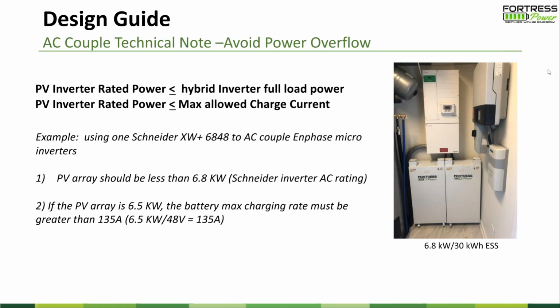And then the PV array - we want to see that it's smaller than the battery bank size. The reason I say this is a lot of PV inverters actually allow you to hook up a little more than what they're rated. If they say it only takes 5K, you can put 6K, because they consider shading, bad weather, productivity, and so on. So that's usually what you want to look at, but we want to consider the worst-case scenario.